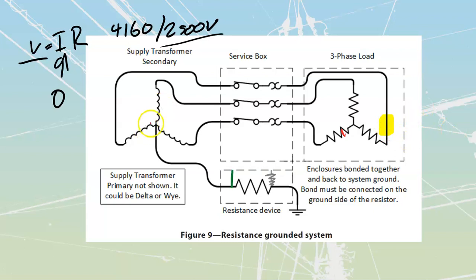We're going to deliver current from our A phase winding over here through my breakers, back down. It's going to hit this fault where it can go across to my bonding pathway, travels along the bonding pathway, and from here is then going to travel—bypassing that resistor—and heads all the way back to the neutral. This would be bad because we would not have any sort of a drop in the current. We'd have unrestricted current that would happen. And if this is on high voltage, we can get a huge amount of fault current.